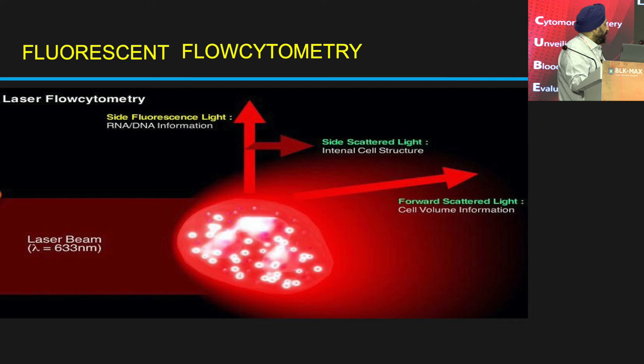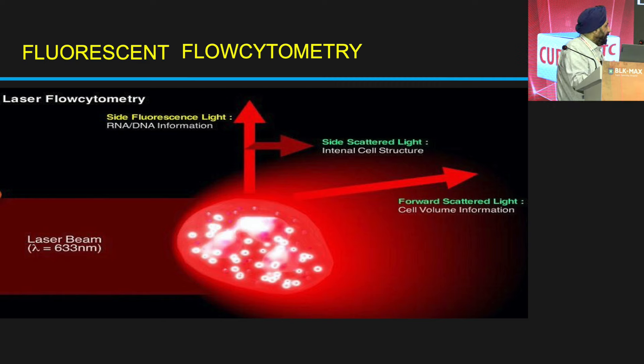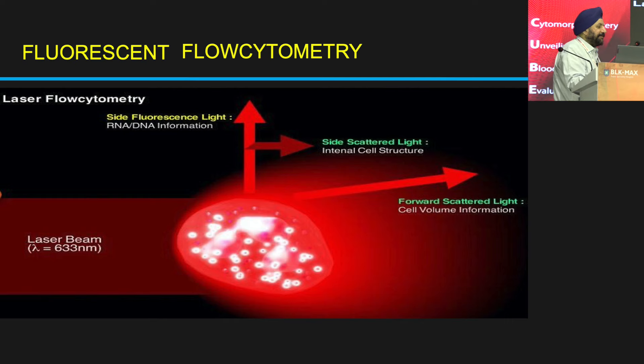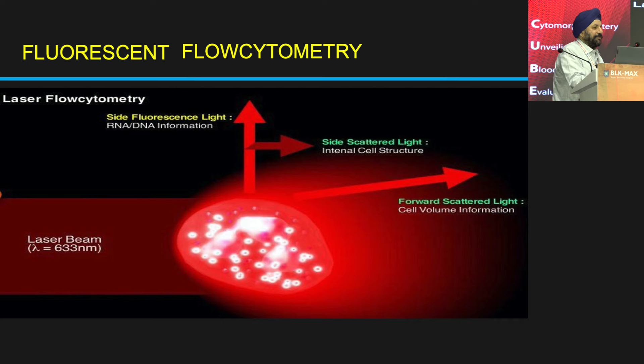We all know that the basic principle of all hematology analyzers is fluorescent flow cytometry, where the forward scatter of the light is depictive of the cell volume or cell size — the more the forward scatter, the bigger the cell. Side scatter shows the internal cell structure or granularity — the higher the side scatter, the more granular the cell. The side fluorescence light tells about the RNA and DNA content of the cell; the more the fluorescence, the more immature the cell.